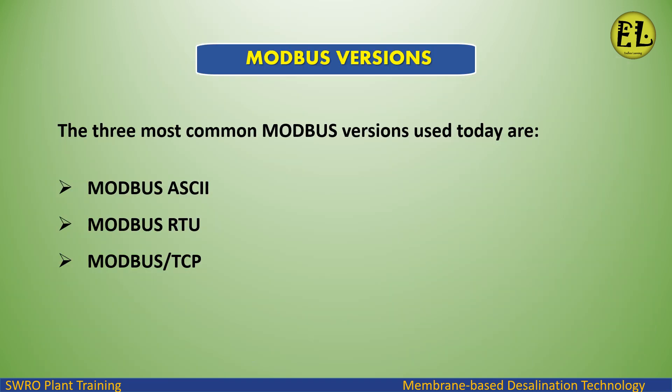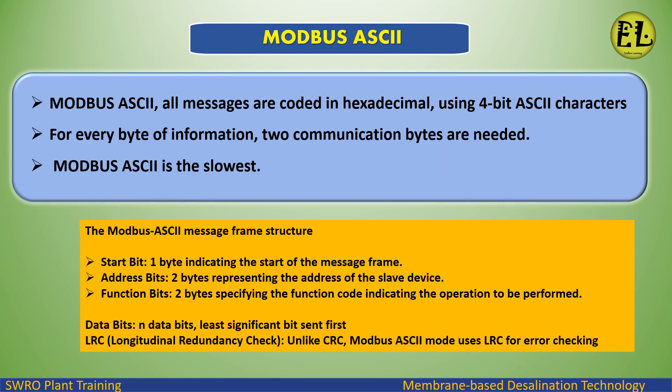The three most common Modbus versions used today are Modbus ASCII, Modbus RTU, and Modbus/TCP. Modbus ASCII — all messages are coded in hexadecimal using 4-bit ASCII characters. For every byte of information, two communication bytes are needed. Modbus ASCII is the slowest version. The Modbus ASCII message frame structure is as shown.